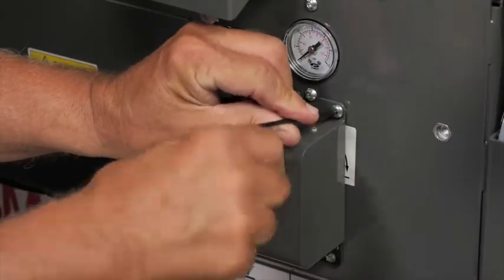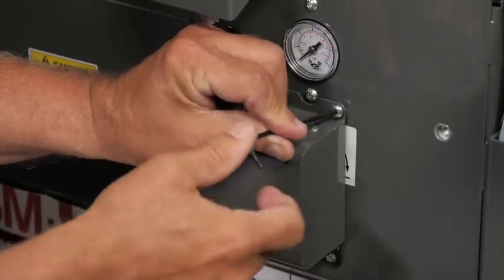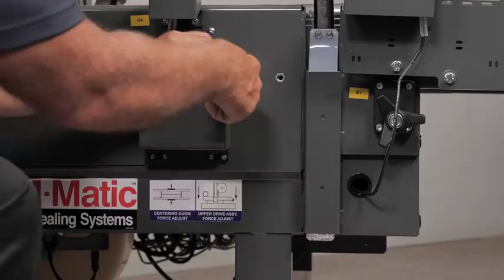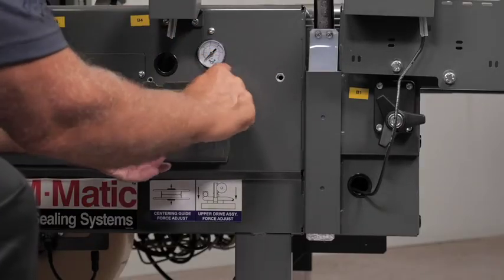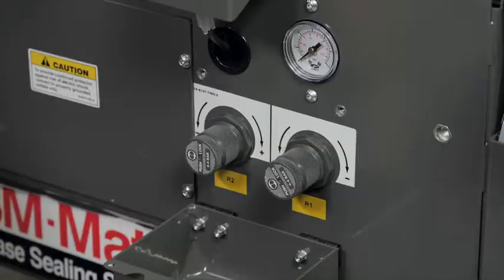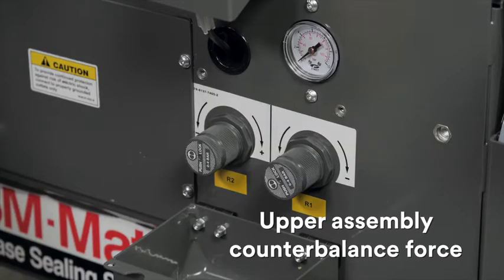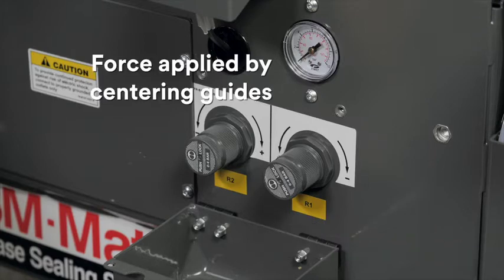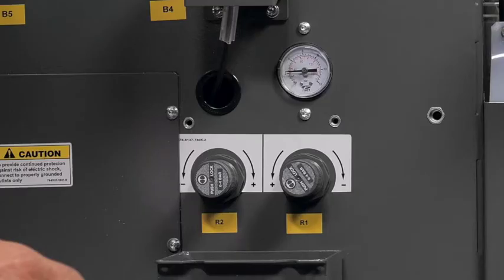Remove the screws securing the regulator cover. The regulator on the right is used to set the upper assembly counterbalance force. The regulator on the left is used for controlling the force applied by the centering guides. Both are preset at the factory. The counterbalance gauge should indicate 38 to 40 psi as set from the factory.